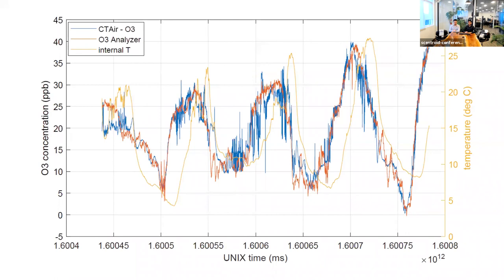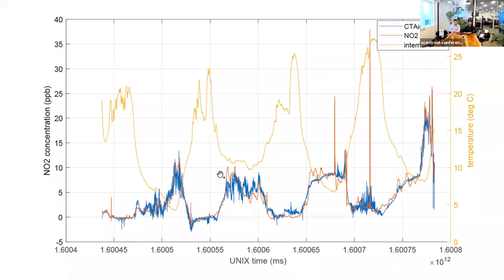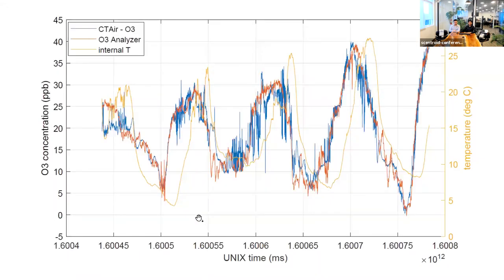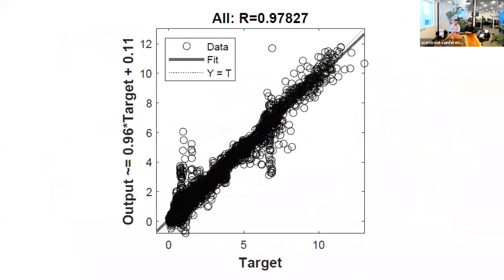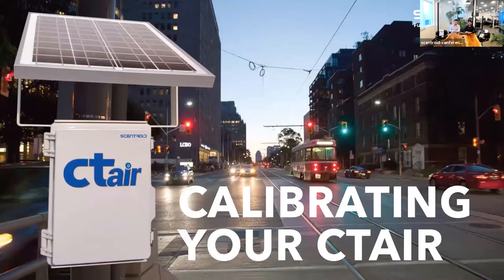Here's a sample of our ozone sensor data, which is basically the inverse of the NO2 sensor — as ozone levels rise, NO2 levels dip. You can see low nitrogen oxide but high ozone readings. This is measured over four nights — the four peaks indicate four days. The ozone sensor readings also match closely with our EPA-certified analyzers, with ranges of 30 to 35 ppb. The correlation data shows an R-value very close to 1, and we're very happy with this performance — it exceeded our expectations.